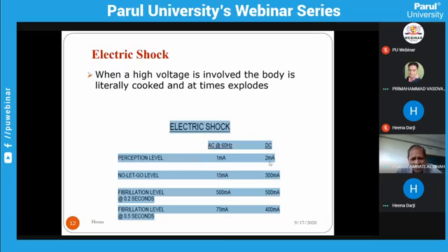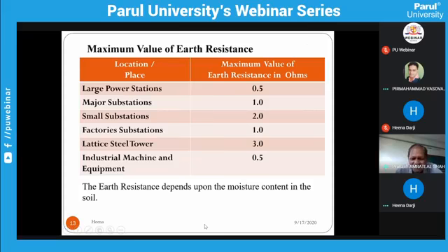Hello. Yes, sir. Our next question is, what can be the earth resistance if a large substation is located at a hilly area? Will 0.5 ohm be applicable for the system? Gentlemen, there are three things deciding the resistance. One is the voltage level. Another is the fault current. By large power stations, you can take the examples of the 1200 megawatt power station at Kevadia Colony, or the Vadakpuri power station where the 800 megawatt unit is installed. In that case, 0.5 ohm is sufficient.